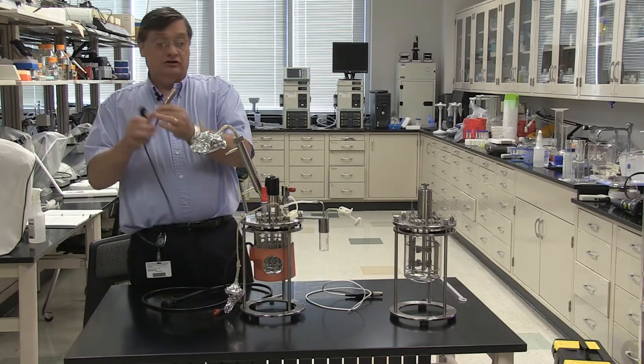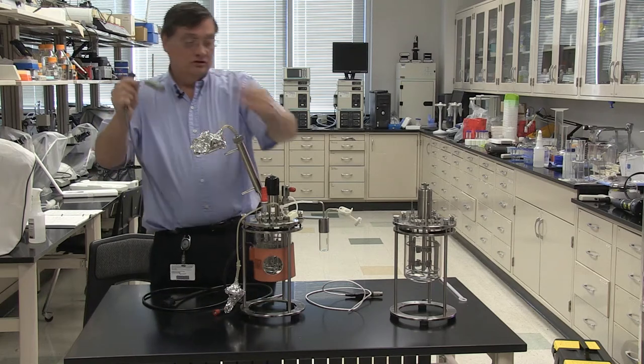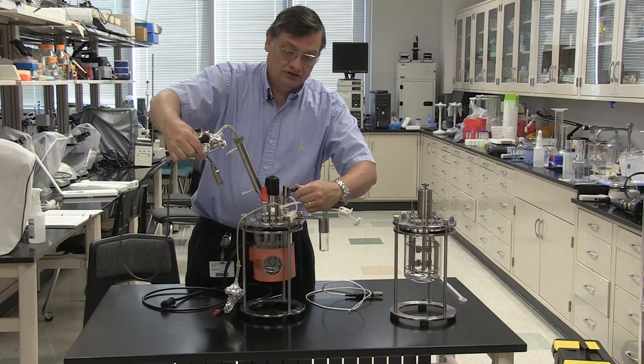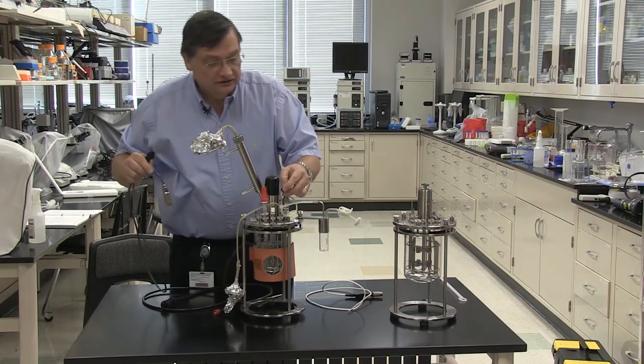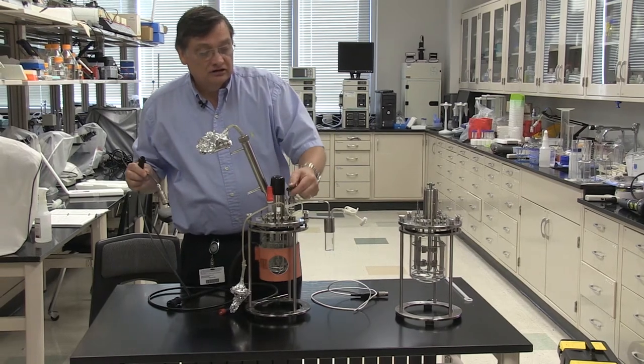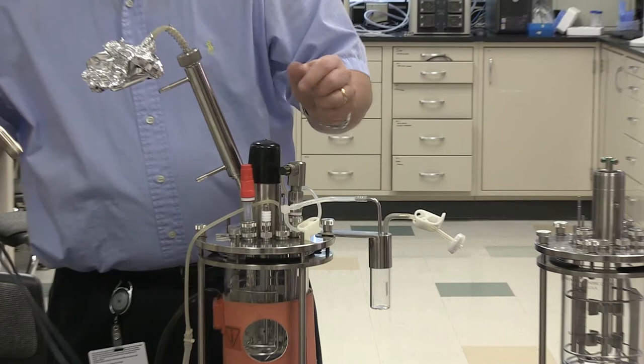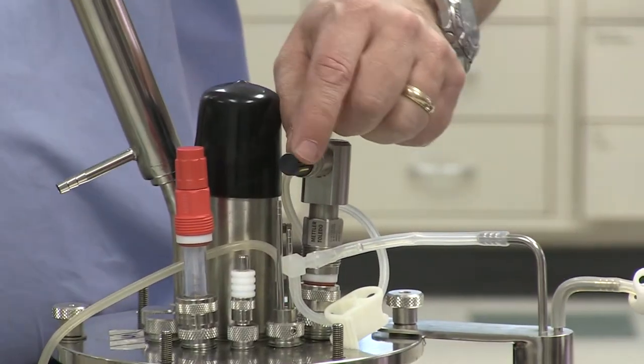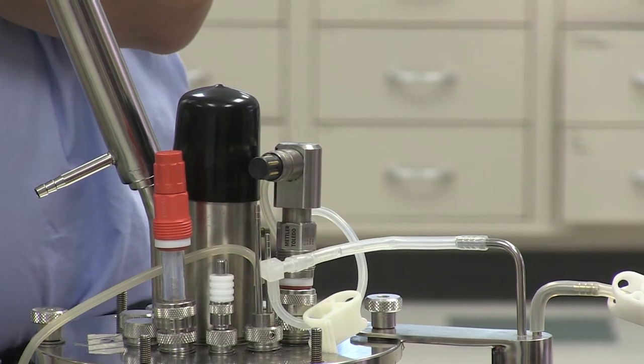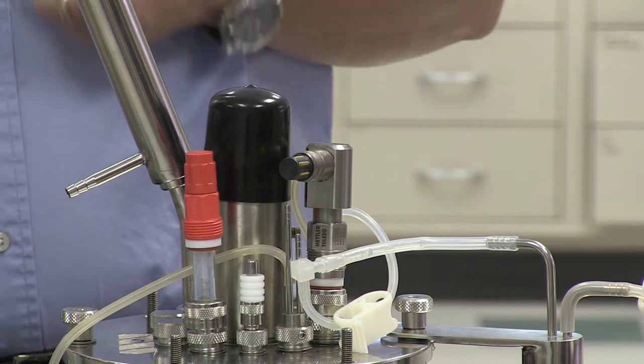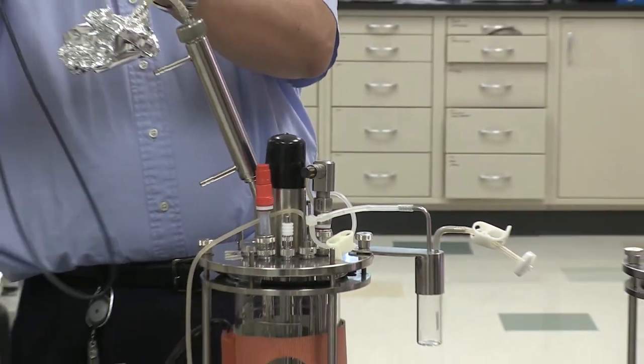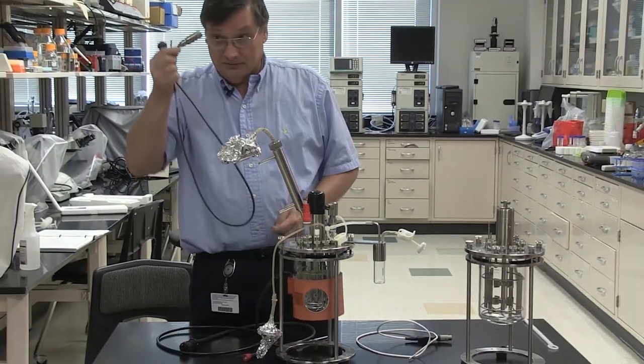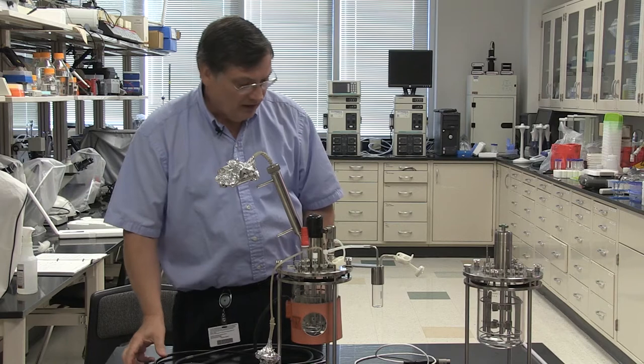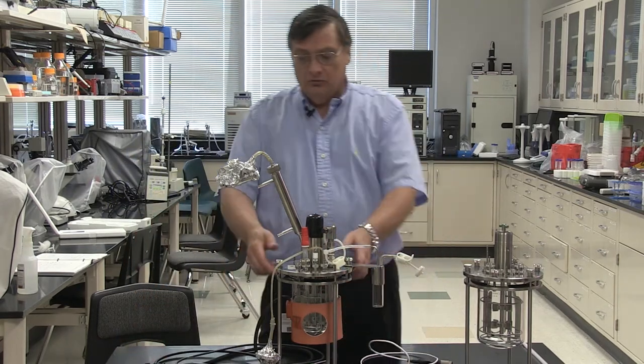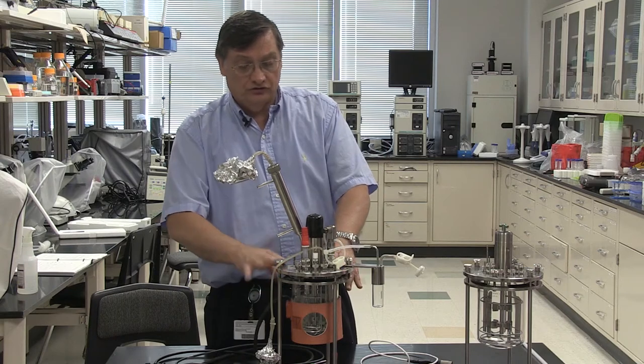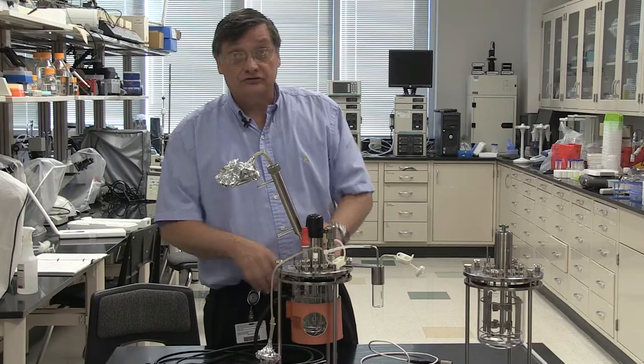This is the connector for the DO probe. So this stainless steel part marries on to where the shorting cap fits on here. Now, it's difficult to see, but there's one little copper connector here that's a little bit longer and bulges out a little more than the other, and there's a place that it lines up. So this is kind of a pain to get on. You just have to make sure that it's aligned properly, and then it'll go on fairly reasonably. But that's for the DO probe. And when we've got the vessel over by the control unit, I'll show you the DO connectors.